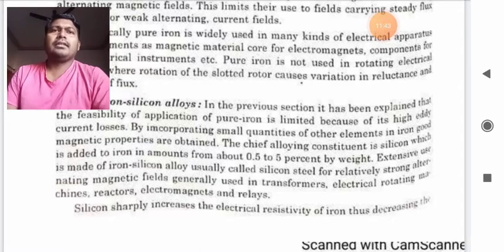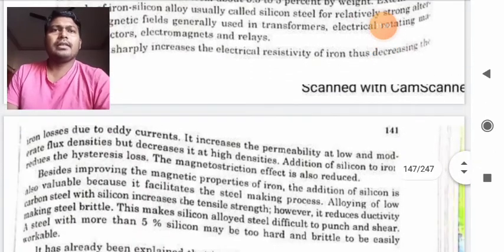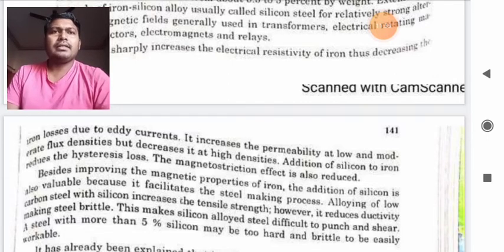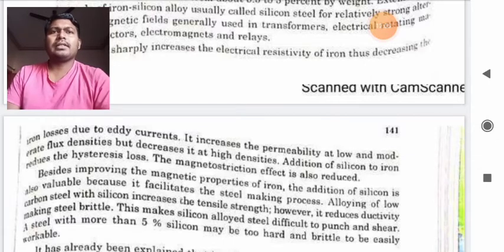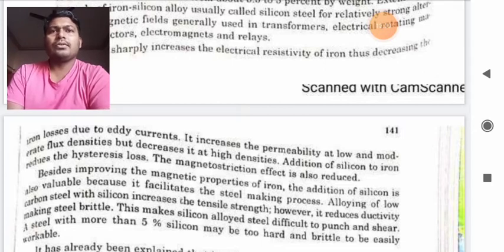Silicon sharply increases the electrical resistivity of iron. Thus, it decreases the iron loss due to eddy currents. It increases the permeability at low and moderate flux densities but decreases it at high densities. Addition to silicon to iron reduces the hysteresis losses. The magnetostriction effect is also reduced.